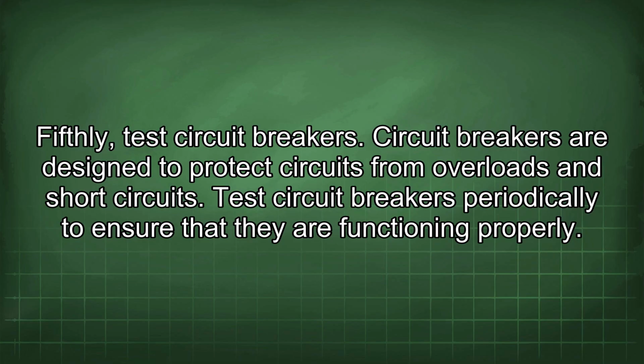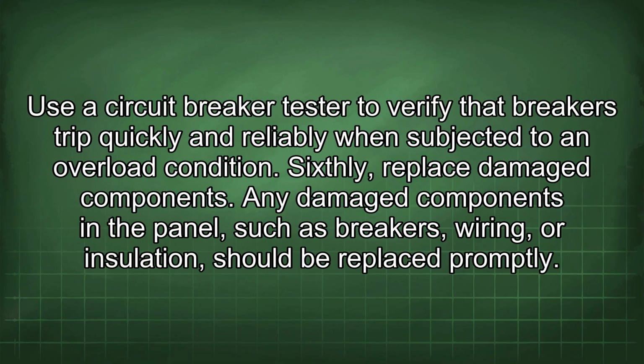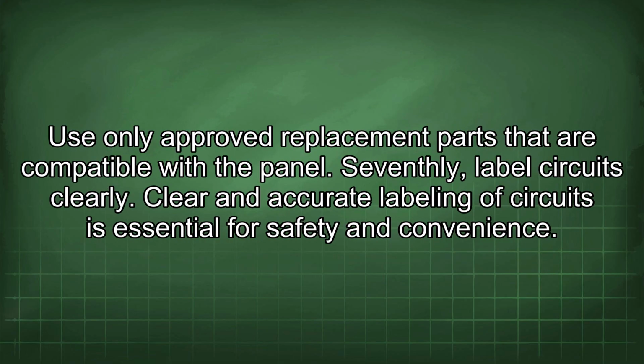Fifthly, test circuit breakers. Circuit breakers are designed to protect circuits from overloads and short circuits. Test circuit breakers periodically to ensure that they are functioning properly. Use a circuit breaker tester to verify that breakers trip quickly and reliably when subjected to an overload condition. Sixthly, replace damaged components. Any damaged components in the panel, such as breakers, wiring, or insulation, should be replaced promptly. Use only approved replacement parts that are compatible with the panel.